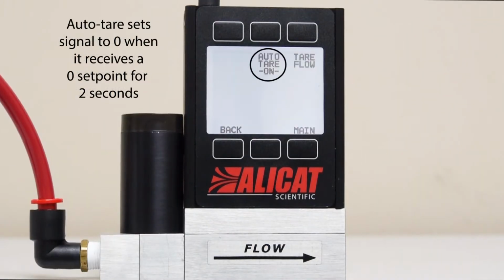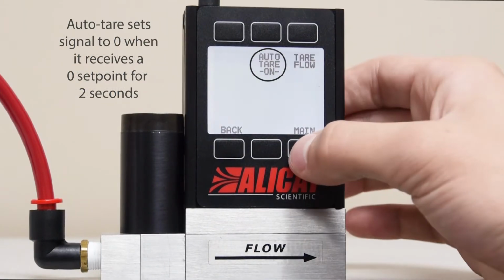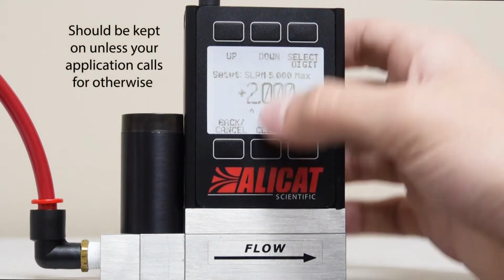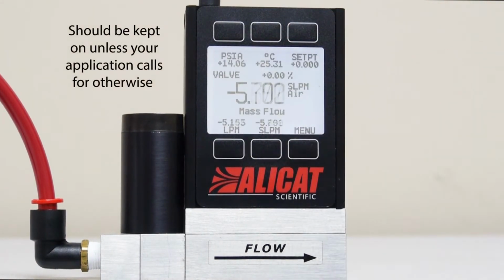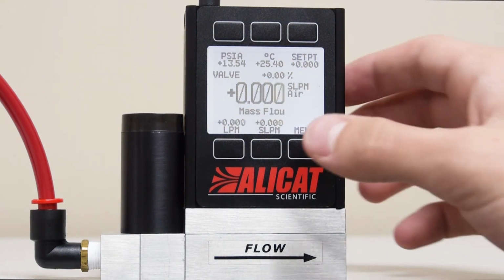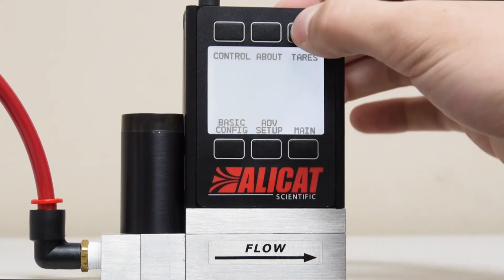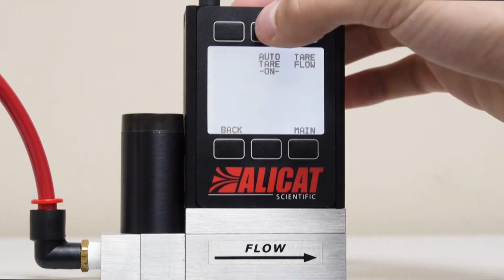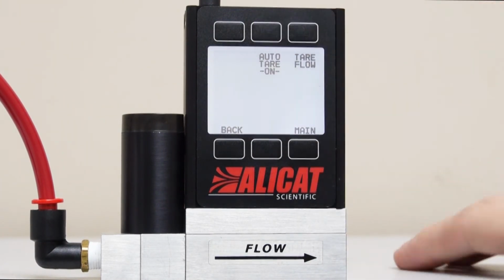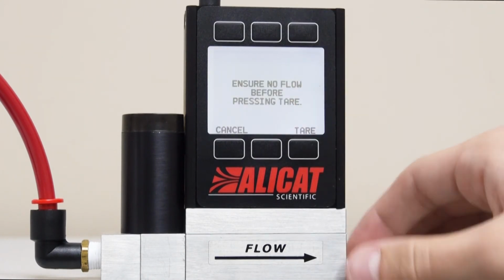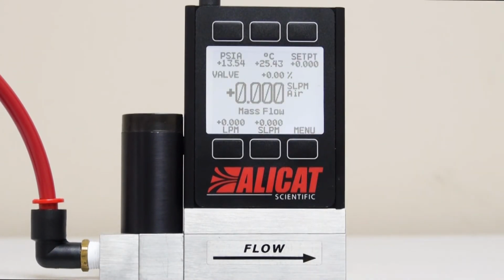The auto-tare function does this automatically when it receives a 0 set point for more than 2 seconds. It is recommended that the controller be left in the default auto-tare on mode unless your specific application requires that it be turned off. To change the tare settings, go to Menu and then Tares. Here you can toggle auto-tare on and off, as well as set the tare for pressure and flow based off the current readings of each.